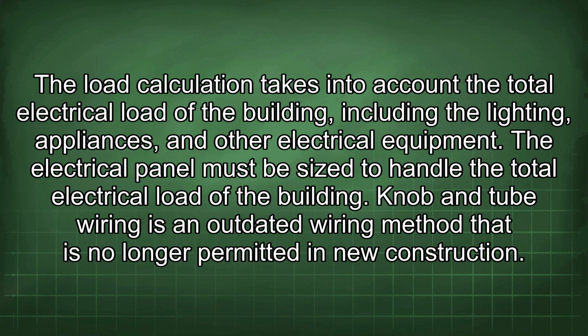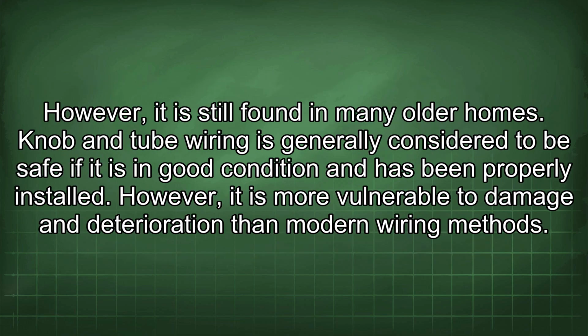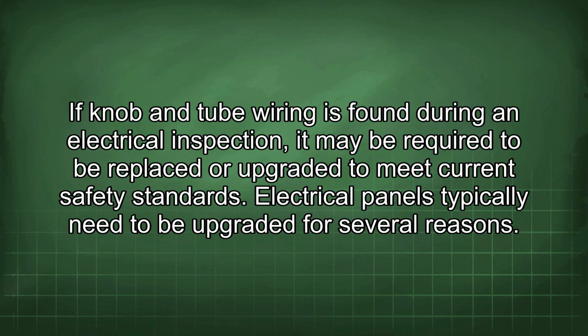Knob and tube wiring is an outdated wiring method that is no longer permitted in new construction. However, it is still found in many older homes. Knob and tube wiring is generally considered to be safe if it is in good condition and has been properly installed. However, it is more vulnerable to damage and deterioration than modern wiring methods. If knob and tube wiring is found during an electrical inspection, it may be required to be replaced or upgraded to meet current safety standards.